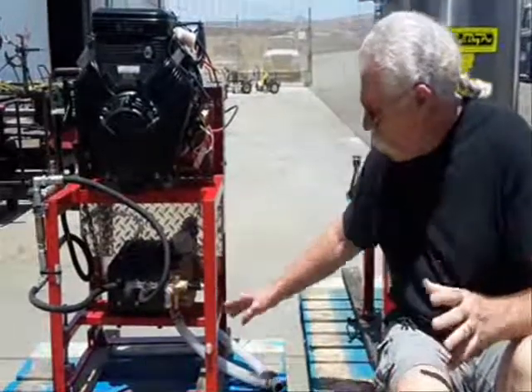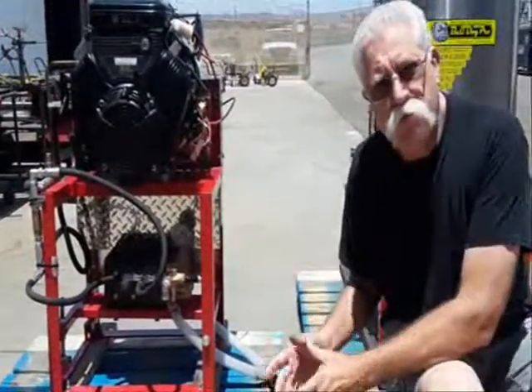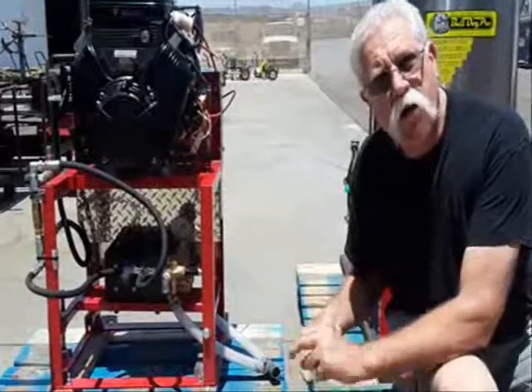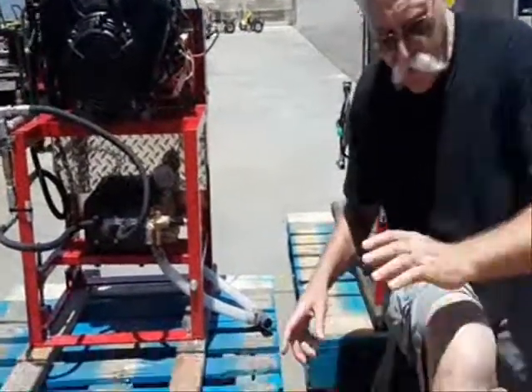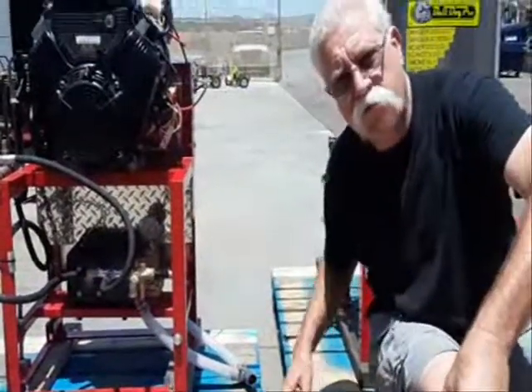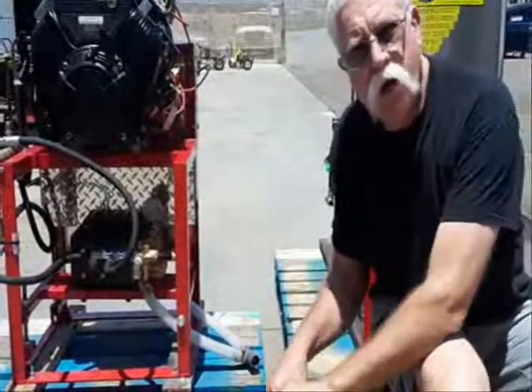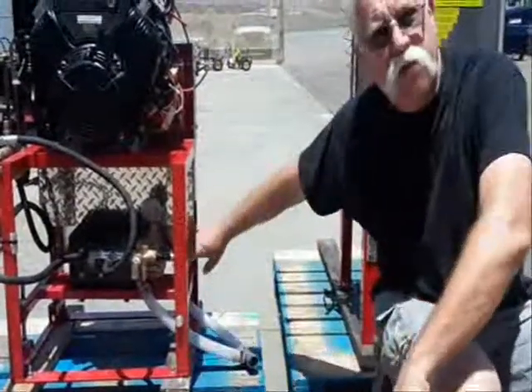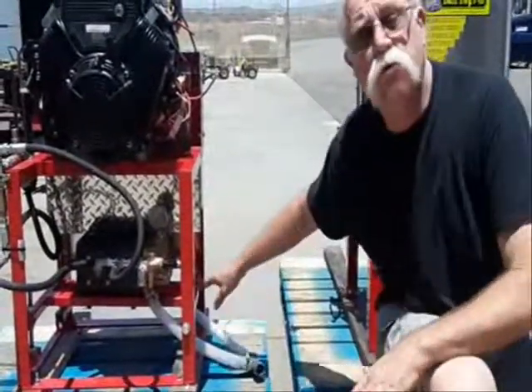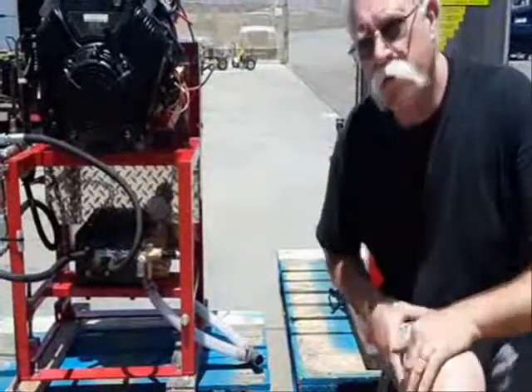long time. Also, on your filter, there's going to be a garden hose adapter so that you can shut off the ball valve that feeds the system, hook up a garden hose to this, and pressure feed the inlet of the system to make sure there's no leaks. That's also great for troubleshooting.